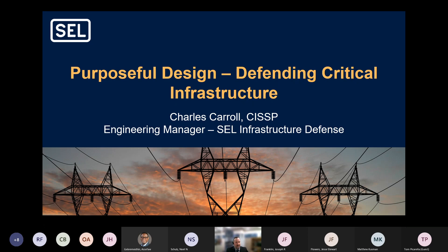For instance, recently I was in Europe and did an assessment on a customer's power system. They had state-of-the-art controls on their IT side — fully virtualized infrastructure and every imaginable IT service. But as soon as you crossed the firewall onto the OT side, or operational technology, almost everything was basically in a default configuration. It should be the exact opposite. A lot of the things we need in an IT environment are unnecessary in an OT environment, so we'll talk about how we can limit or disable some of these things and improve security.